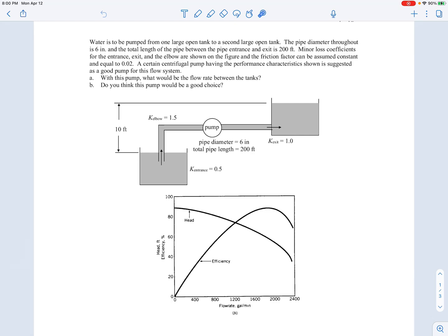To find the flow rate between the two tanks, we'll find the system curve using the extended Bernoulli equation — this tells us what head rise is required from the pump to get a certain flow rate through the pipe. We'll then see where the system curve intersects the pump curve, and that will be our operating flow rate. The idea is the system requires a certain head rise for a particular flow rate, and the pump can provide a certain head rise as a function of flow rate; we find where the two exactly balance.